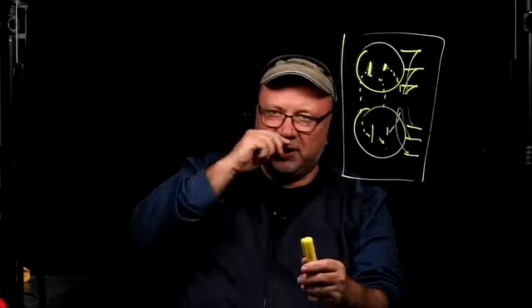Sometimes you might want to interrupt that link, so you have a separate hot wire going, or you can interrupt the whole thing so you have 2 separate cables going, but usually the hot one is interrupted. The neutral services both of them, and the hot wires go separately, but that depends on what you want to do - so you can separate them. That's called a split receptacle. Usually those are installed around kitchen cupboards where more current is needed, especially in the morning - let's say if you plug in a toaster in one of them and something else like a coffee maker in the other one, that may take more current.